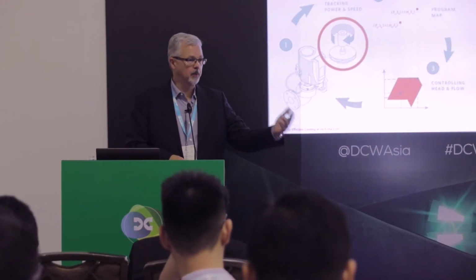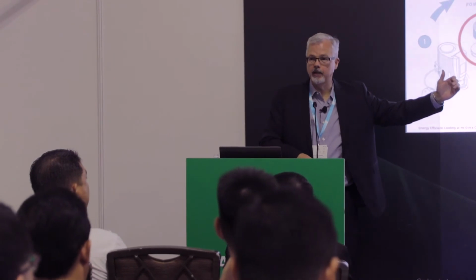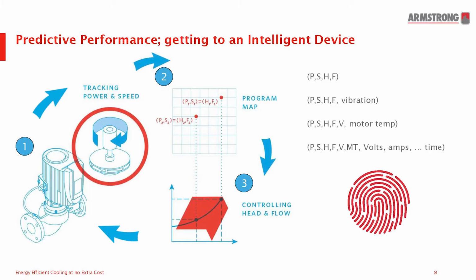Then we can amp it up and go all the way out to time. So this intelligent device living in that mechanical room space sees a certain characteristic every day, and after 5 years of learning and experiencing a continuously repeated trend of load, flow behavior, and valve position behavior, there are things we can do to be anticipatory and make the system perform better so there isn't a lack of flow when that valve starts to open.